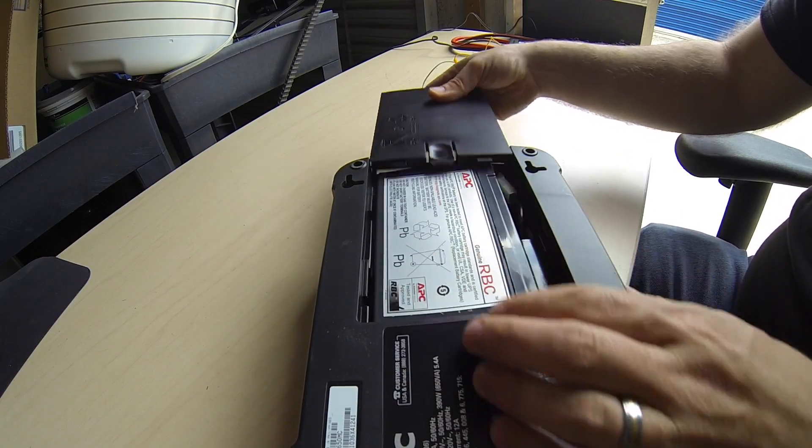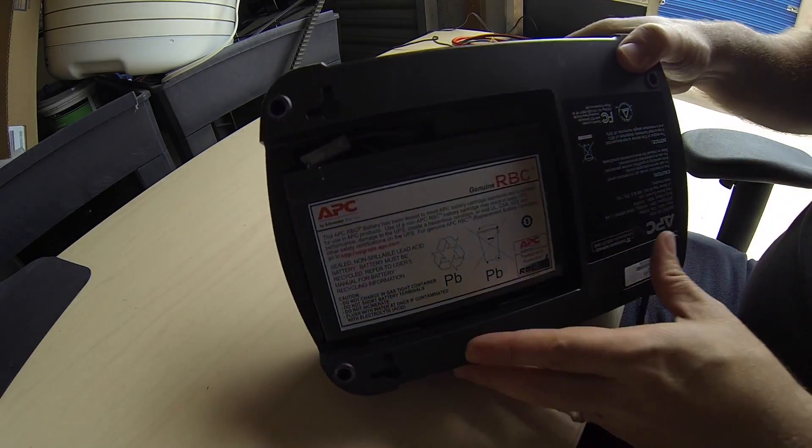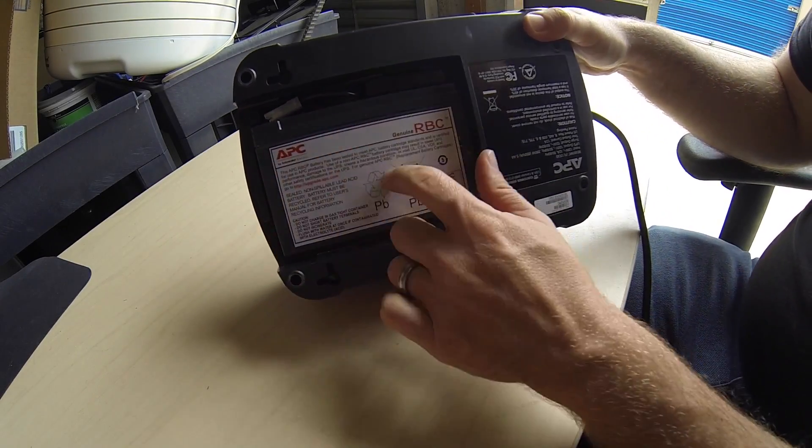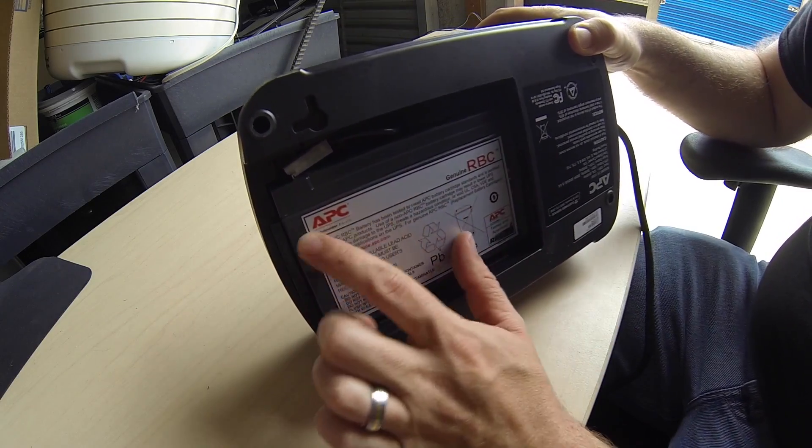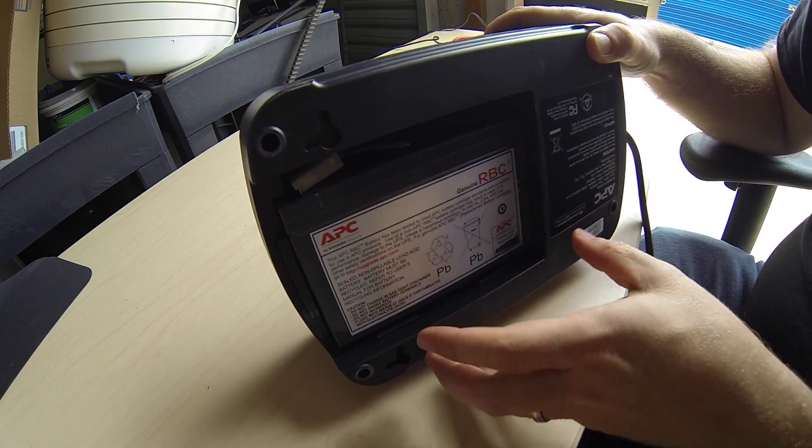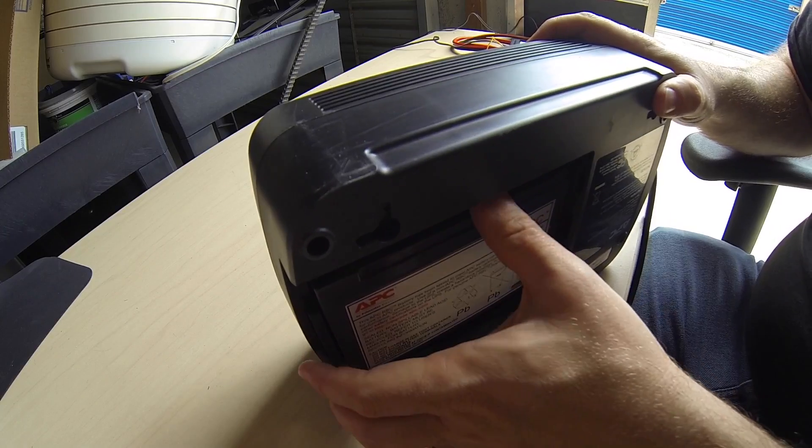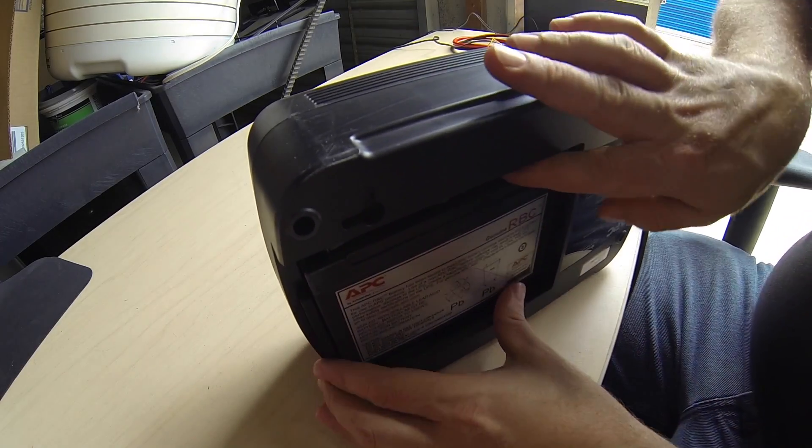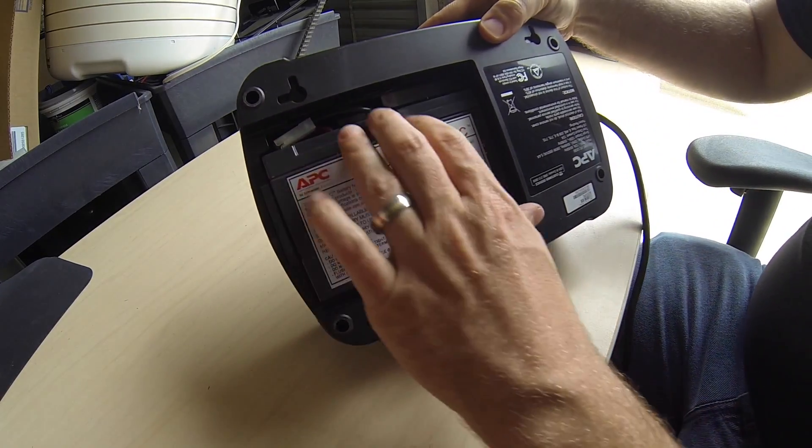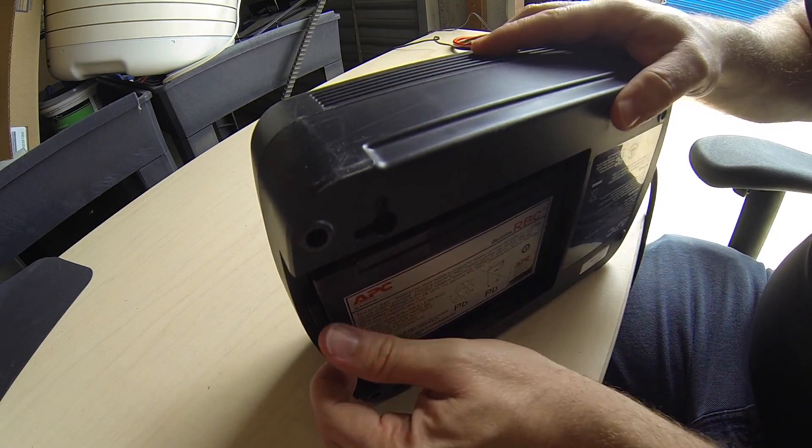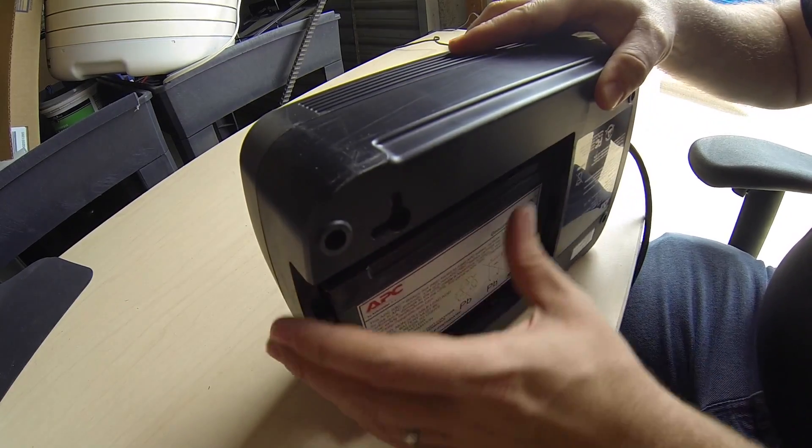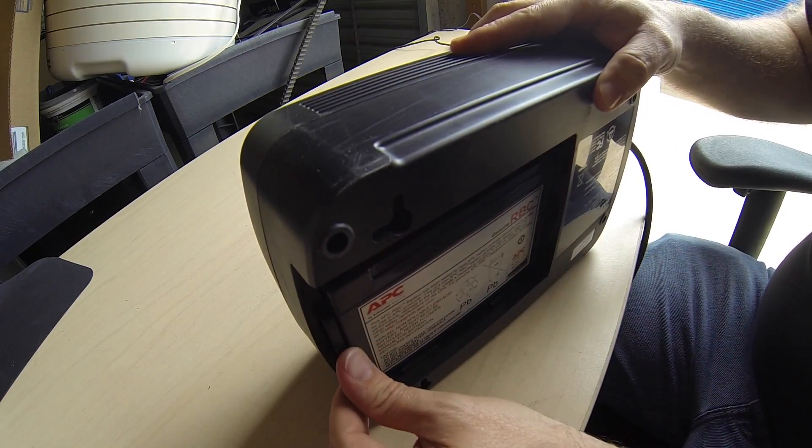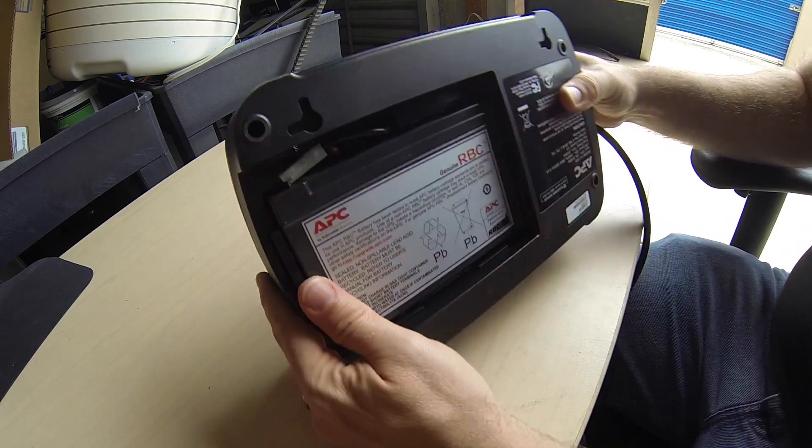Open up the back like this. And this is the original battery because people don't buy APC brand batteries to replace them. There's nothing wrong with buying a local battery. This one's stuck so it may be swollen in there and that's likely the problem why this guy doesn't work. I'm going to need to grab a screwdriver to pry it out of there.